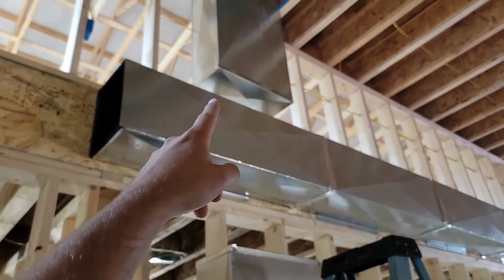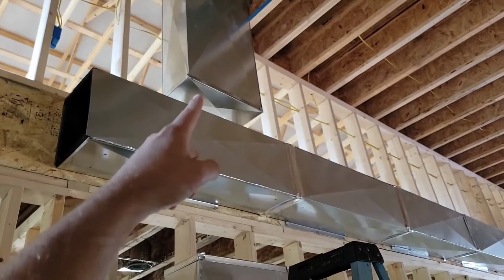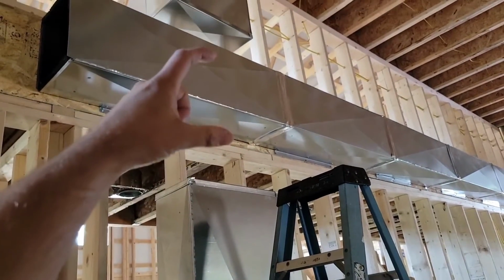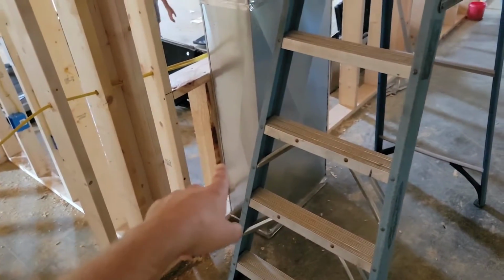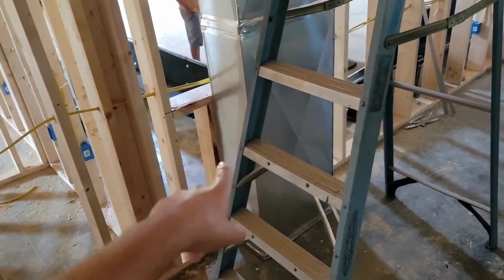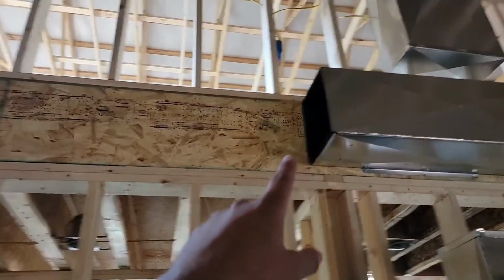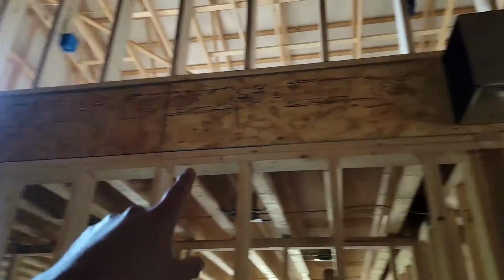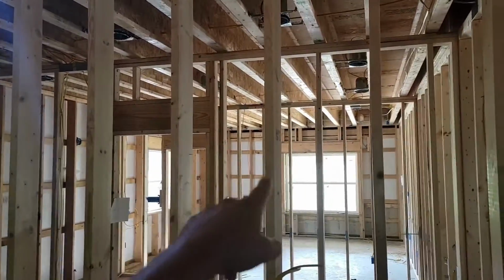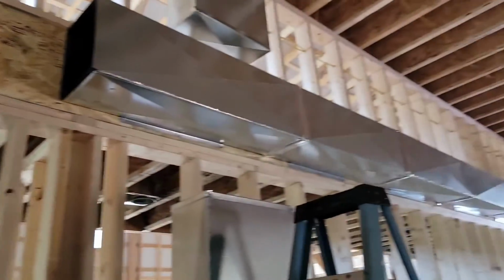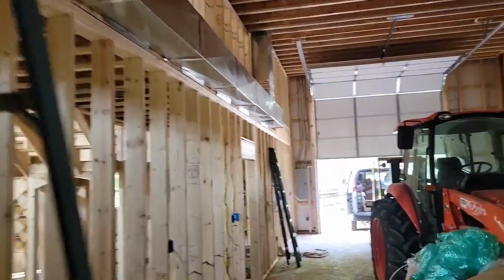Ended up finding a better way to run the return. Instead of running it in the closet here, they ran the return straight down, and Nick is going to build a square 90, then a piece of straight square duct, and then another square 90 to reconnect that return. This will be where our lower return is - both returns will be the same, 20 by 25. I'll show you the other side of that duct, and then they may run this trunk out a little more to get these lines in here, these ceiling vents we're going to install.